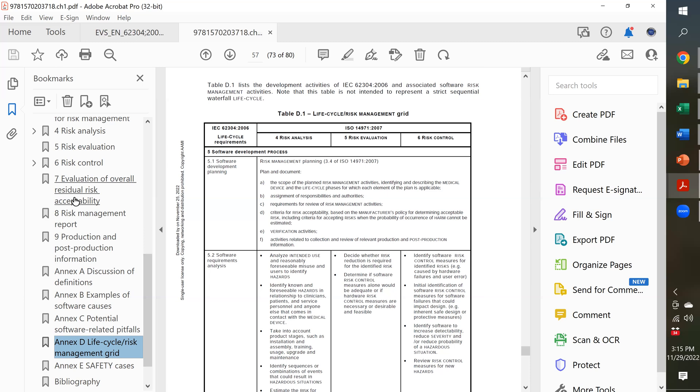So, therefore, the more appropriate tool than doing an FMEA or a design FMEA would be to use a fault tree. This is a much better tool, it's a top-down approach, makes it easier to work backwards whenever you have a complaint or somebody from technical support heard, hey, I think we have a bug.